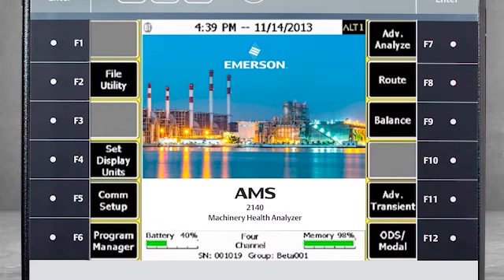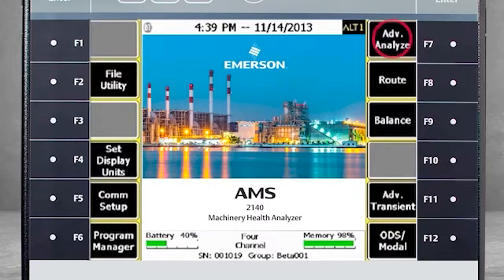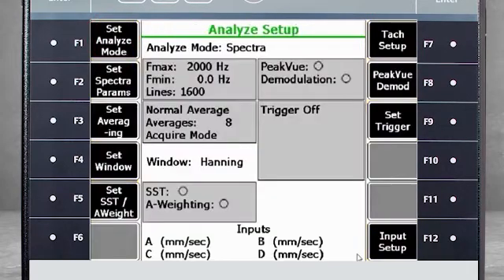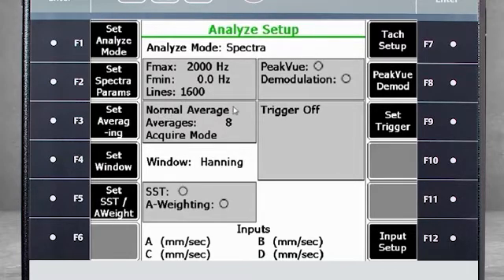Now let's look at the AMS 2140. Here you see the home screen of the analyzer. We'll walk you through data collection on a variable speed machine using normal averaging first, then repeat using the order tracking process. Select F7, Advanced Analyze, and then F1, Manual Analyze. Here you see the settings to collect 0 to 2000 Hz with 1600 lines of resolution, normal averages, and 4 inputs. I will now start the machine to collect data. The speed will change frequently while we collect data.